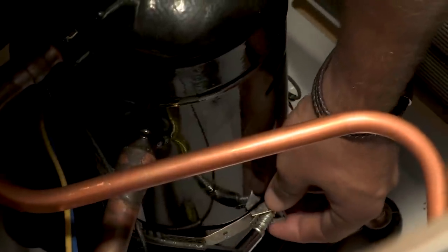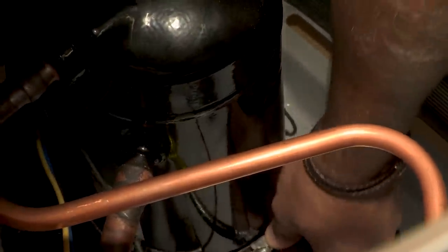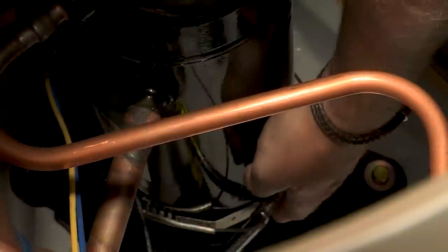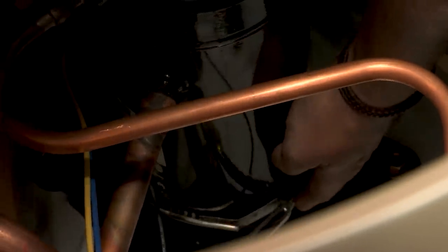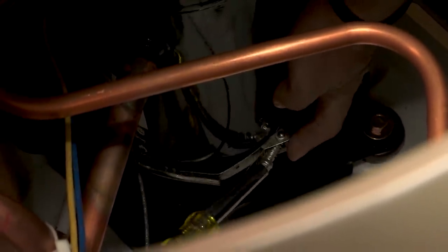Do I want it at the bottom or in the middle? Does it matter? Probably the bottom. You want it at the bottom of the compressor. That's the coldest point. Well, it's where the oil would be. You don't need to heat the oil, you're trying to heat the case. No, you're trying to heat the oil, that's why it's called a crankcase heater.